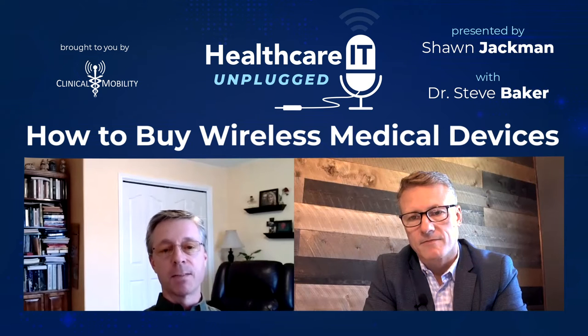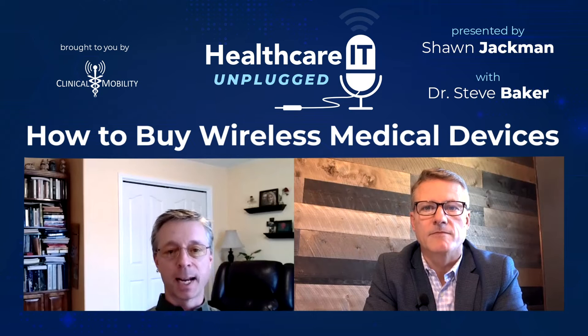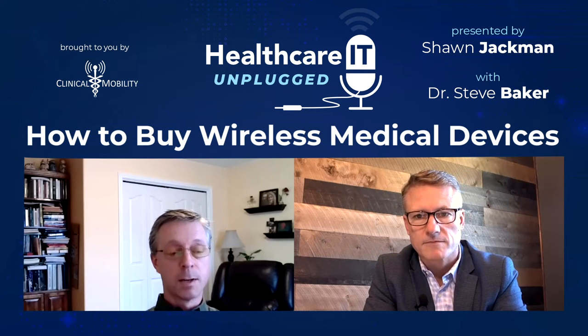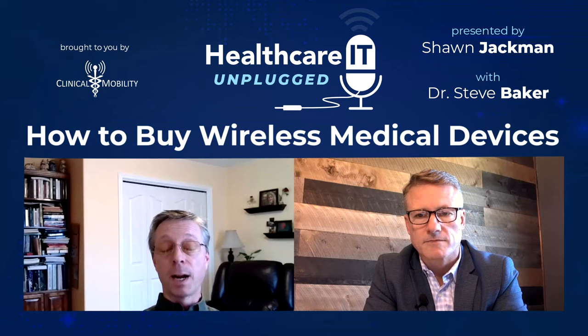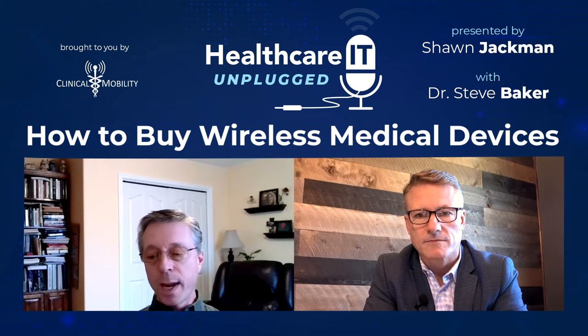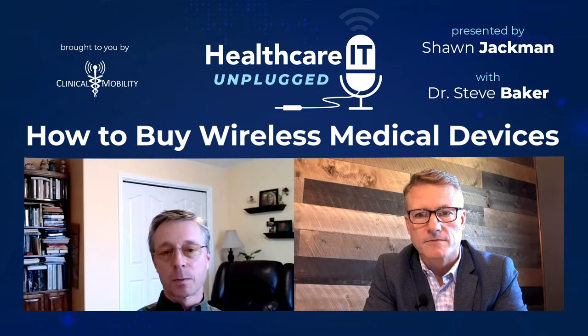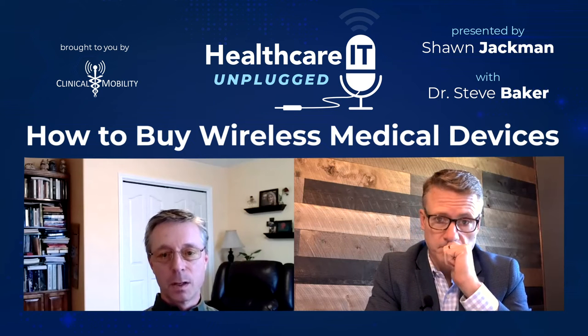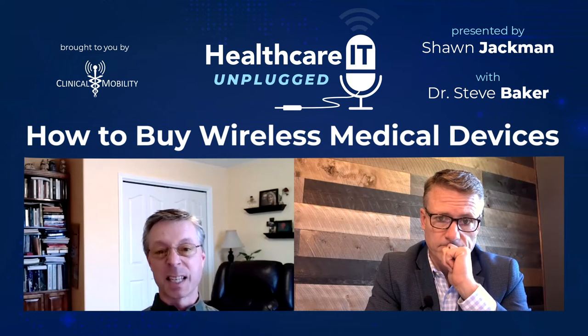So the FDA gives medical device manufacturers rules on how much validation and verification testing we need to do to make sure the replacement is valid. A lot of times we can find a sister processor that does the same functionality. What's important for us is that it has the same pinout, so it's easy.